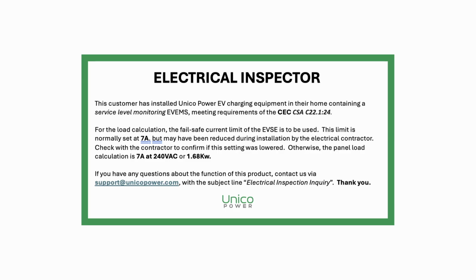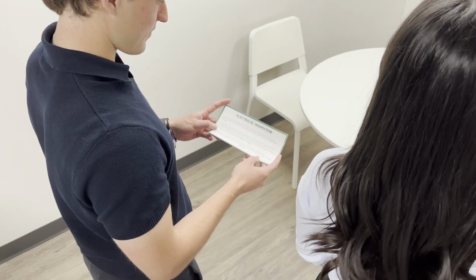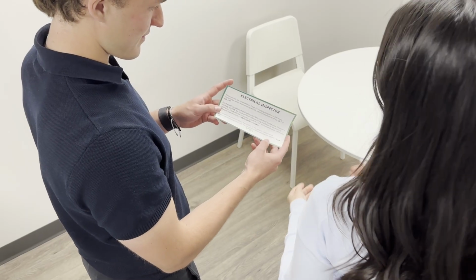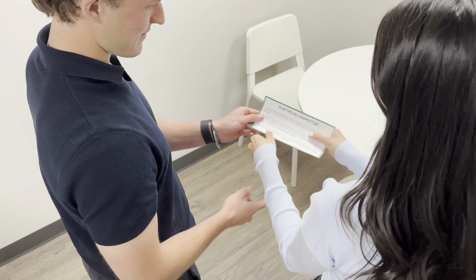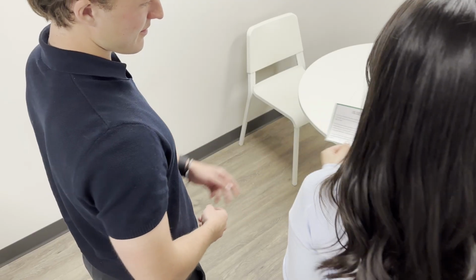them the paper slip titled Electrical Inspector. This slip explains how Listo EMS is a CSA-certified EV EMS and that the EV charging load is treated as a 7, 6, or 0 amp continuous load. If the inspector is not present, ensure the customer holds on to that paper slip for when the inspector does get to site.